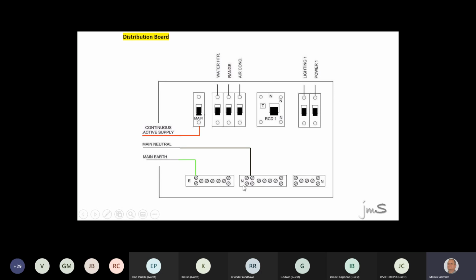0. But if you put a link in, and that's 10 amps, then 5 and 5 goes back. This Earth now carries operational current. And 3000 says in the testing, the Earth is only allowed to carry fault current. That's why a DB is not allowed to have a link. Make sense? Cool. Right, the wiring's the same.